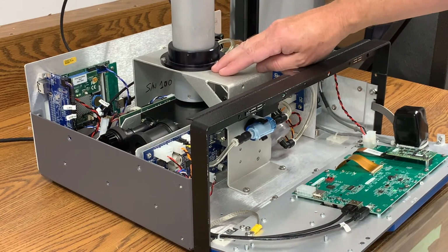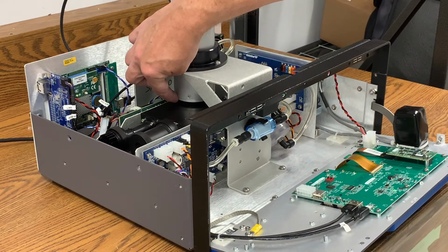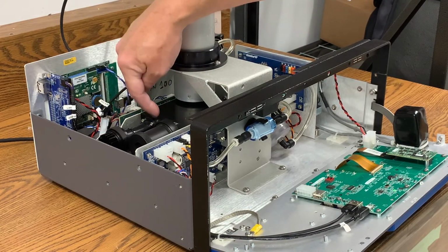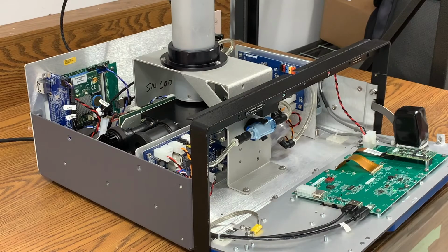Then the air flows through an optical particle sensor. A light shines through a chamber and is scattered by the particulate matter that flows through the air. The intensity of the light scattered defines the size of the particle, which the instrument is able to read and display for the operator.